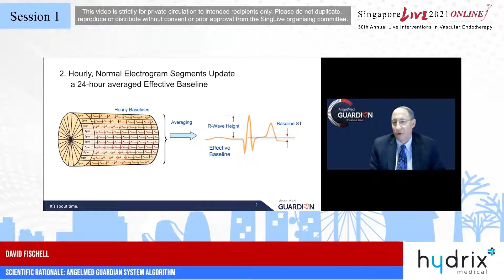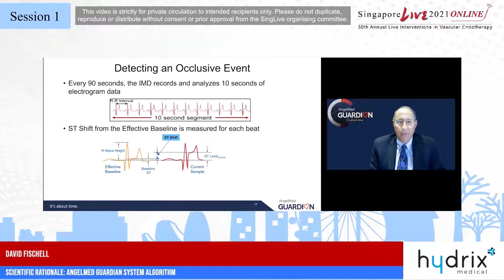Now that the IMD knows what's normal over the last day and has excessive ST shift thresholds based on thousands of measured beats, the IMD looks to detect an occlusive event as follows. Every 90 seconds, 10 seconds of electrogram data is analyzed. Sinus beats are compared to the effective baseline to see if the ST level for the beat has shifted more than the detection threshold. If 6 out of 8 beats are shifted, the IMD waits 20 seconds and then grabs another 10 seconds of data, and it does this in successive segments. If 6 out of 8 beats in 3 successive segments are shifted, the Guardian initiates an emergency alarm.